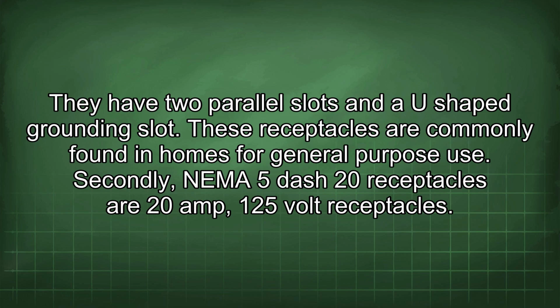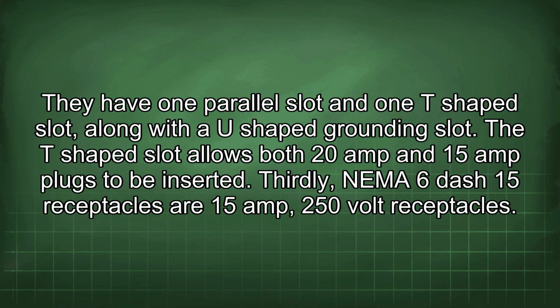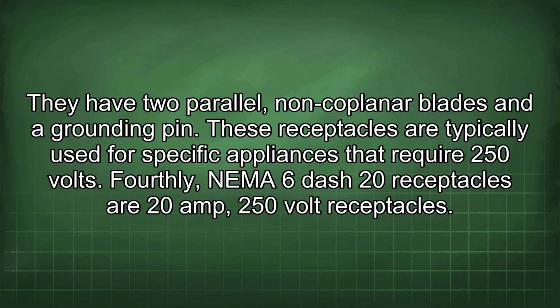Secondly, NEMA 5-20 receptacles are 20 amp 125 volt receptacles. They have one parallel slot and one T-shaped slot along with a U-shaped grounding slot. The T-shaped slot allows both 20 amp and 15 amp plugs to be inserted. Thirdly, NEMA 6-15 receptacles are 15 amp 250 volt receptacles. They have two parallel, non-coplanar blades and a grounding pin. These receptacles are typically used for specific appliances that require 250 volts.